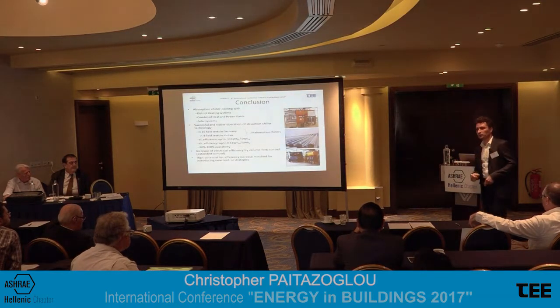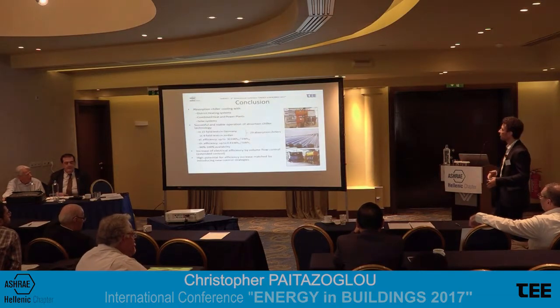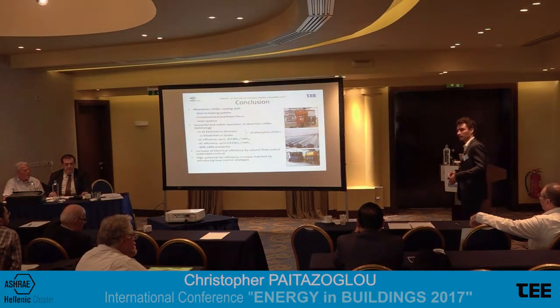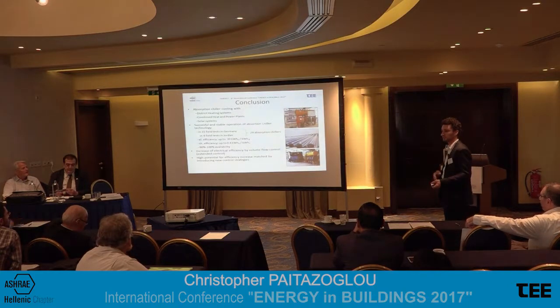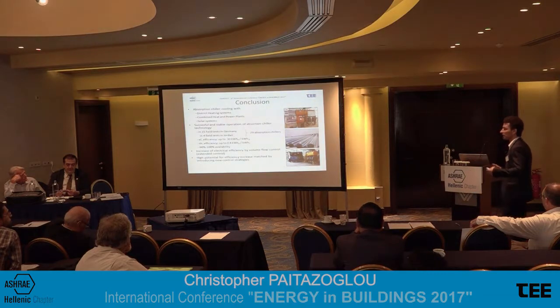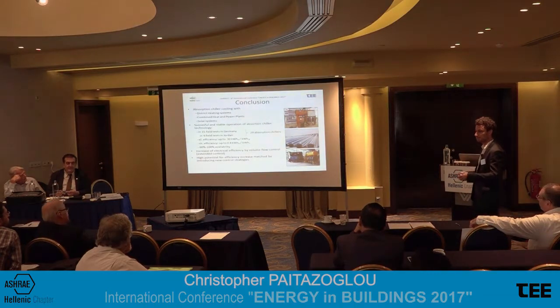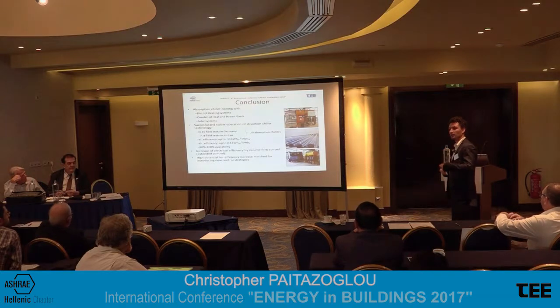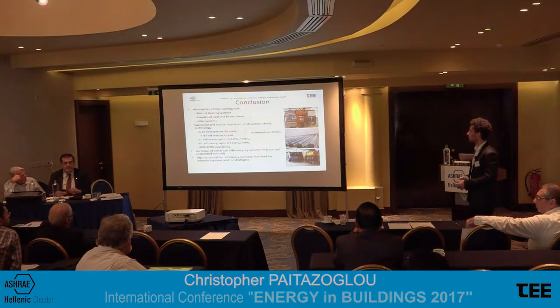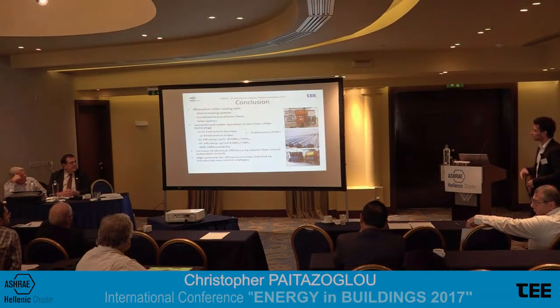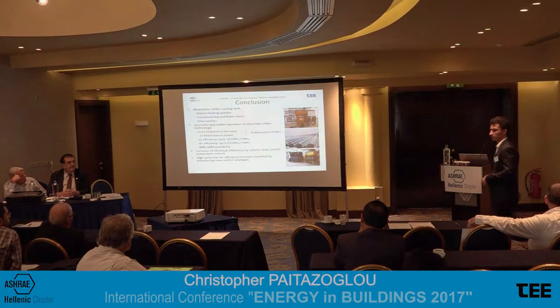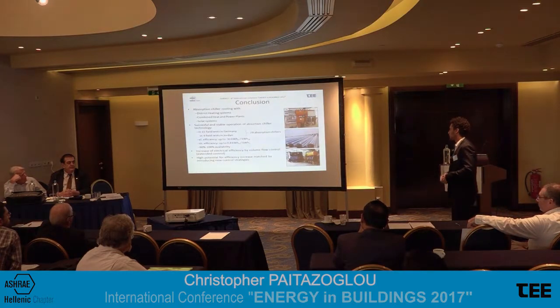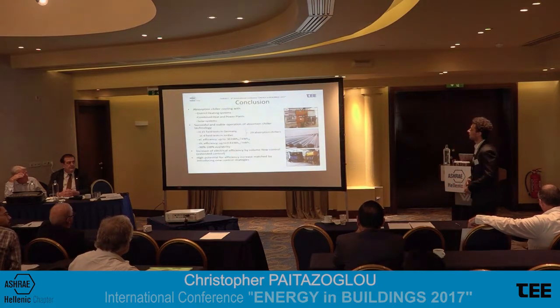So I would like to conclude. We saw that absorption chiller cooling is possible with different high temperature heat sources. These are heating systems, which are quite common in Germany. I heard they are also common in Greece. Then combined heat and power plants, which have their own demands, a fixed temperature difference in their hot water circuit, and also solar systems, as we saw in the slide before. We saw that the operation of those absorption chillers is successful and stable. In the last years, we only saw the monitoring points from 2016.